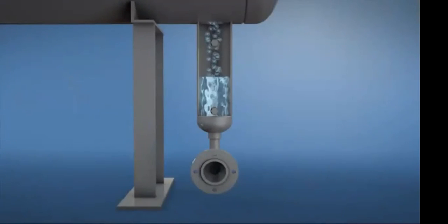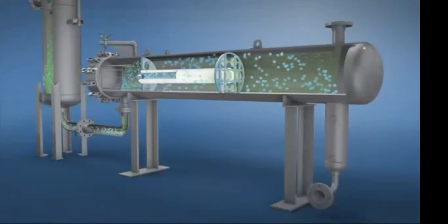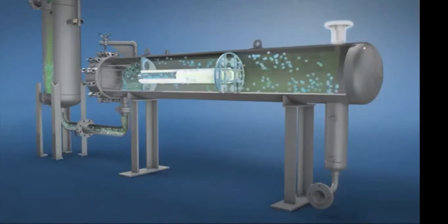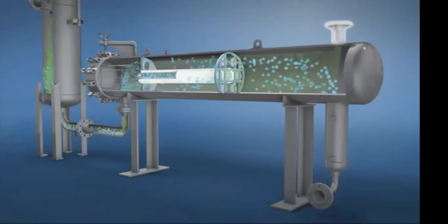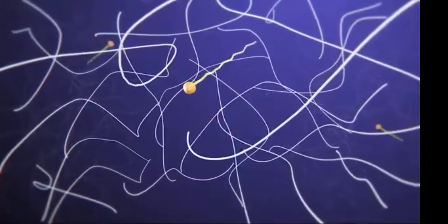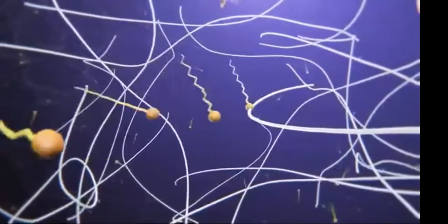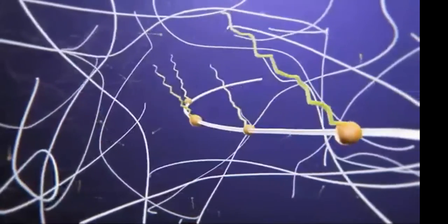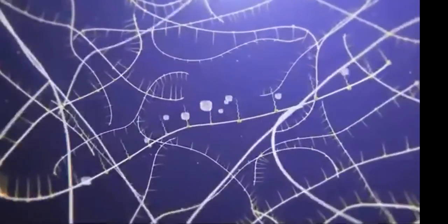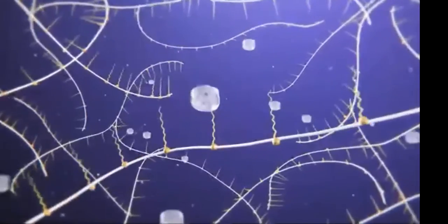The free water is accumulated in a collection boot. The purified hydrocarbon flows out the top of the vessel onto downstream processes. Unlike Pall's polymeric coalescers, conventional glass fiber coalescers are known to absorb surfactants, progressively coating the fibers. When the small water drops approach the disarmed glass fibers, they are repelled and no coalescing occurs.